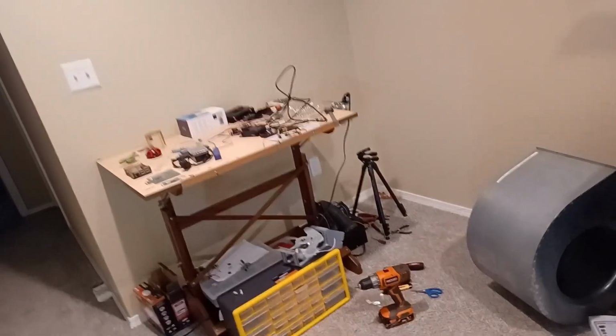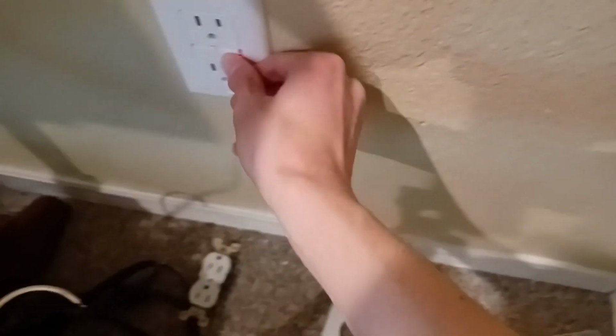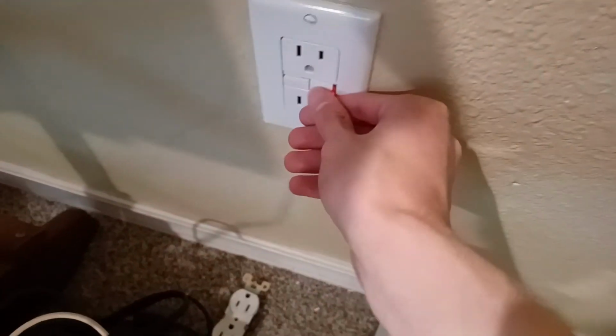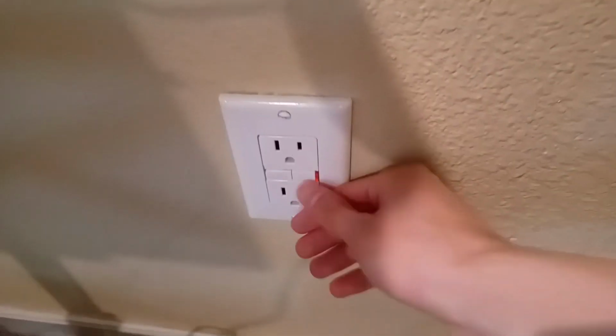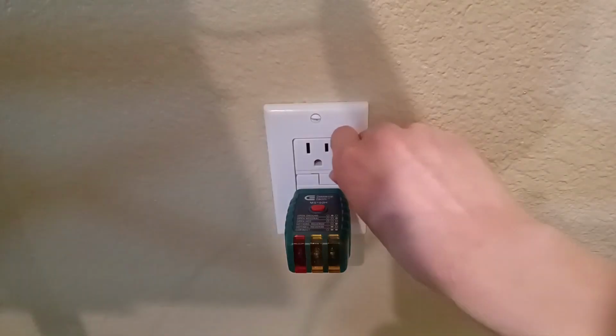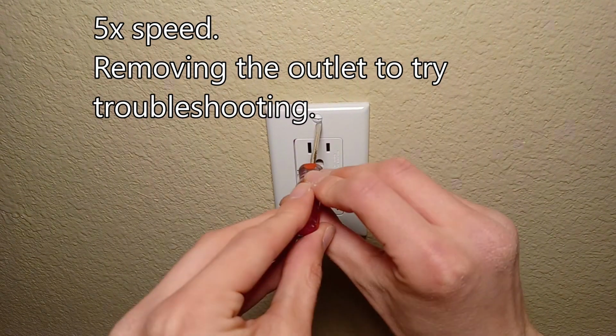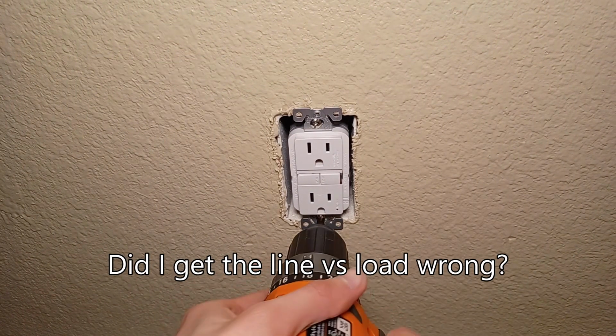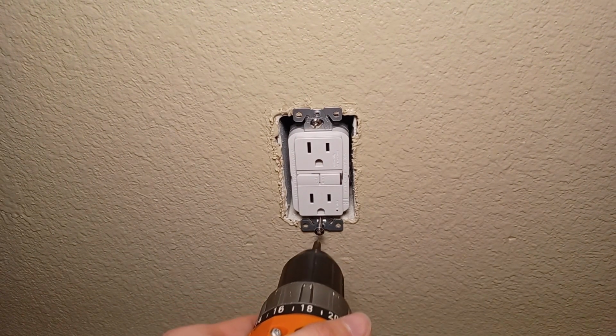Oh, what happened? I tripped it pulling it out of there. There's something plugged into here that's shorting it out. Let's try turning this back on. Oh boy. Is my tester broken? Something's wrong with this. It gives power and then cuts it off. Turn back off the circuit breaker. Did I get the line versus load wrong? I don't think I did.